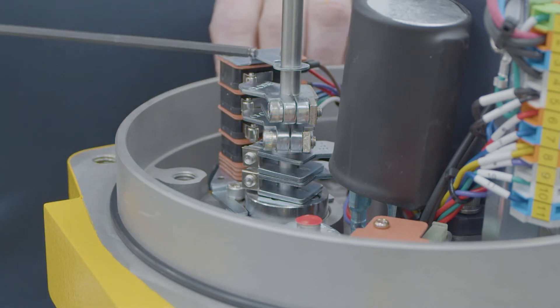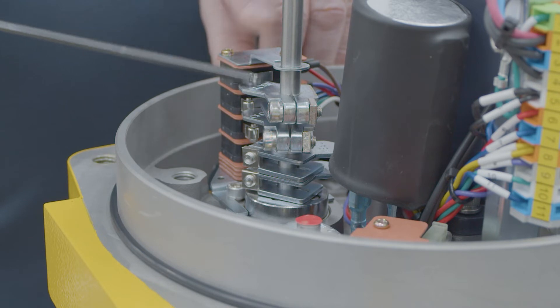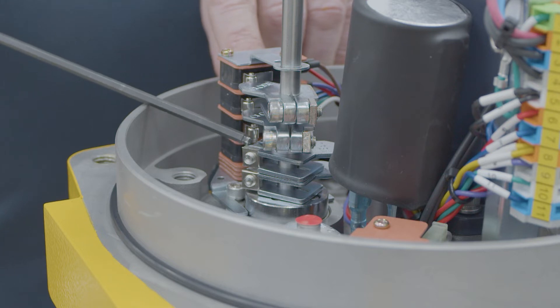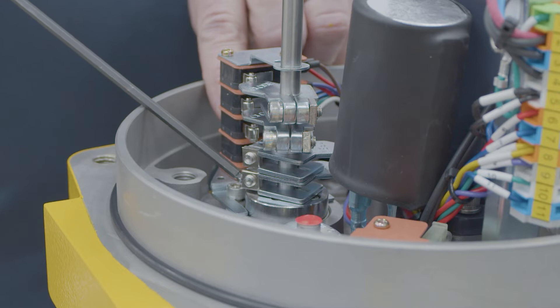So your top switch is your clockwise or your closed for your motor stop. Your second is your auxiliary for your closed. Your third one down is going to be your open or counterclockwise for your motor stop. And then the fourth one is going to be your auxiliary for your open.